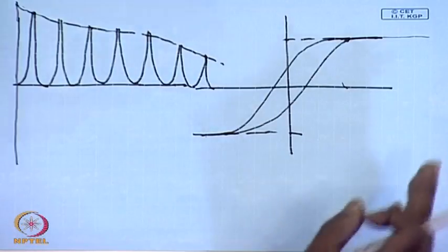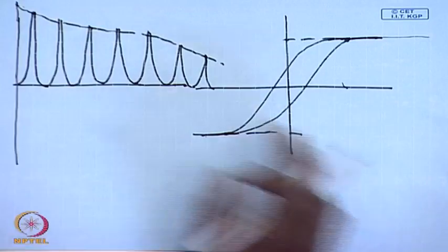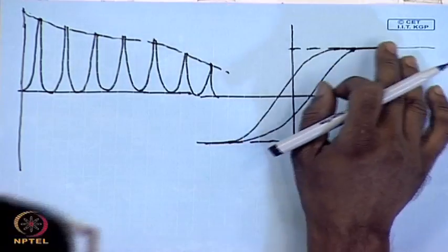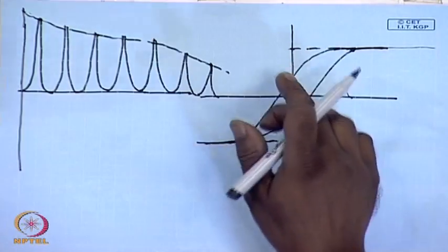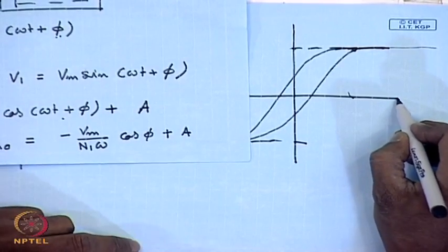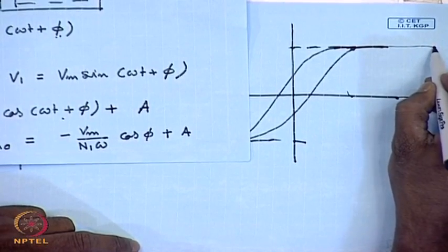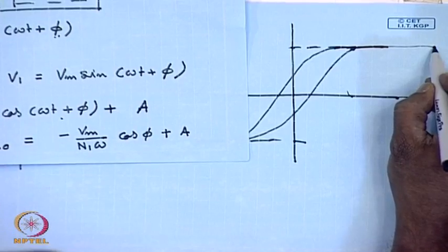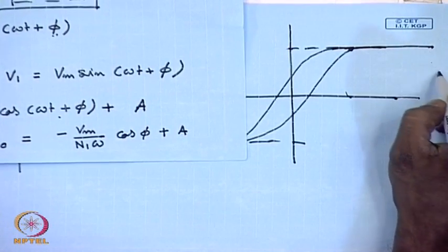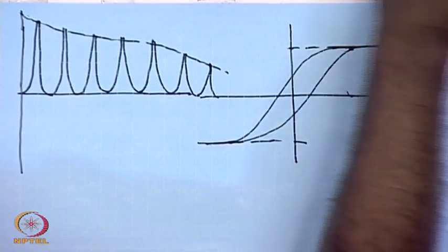Methods have been developed to detect the voltage waveform and switch transformers accordingly. Please note that the situation will be worse if there is some residual magnetism in the flux, because in that case the peak value can be even larger than twice the steady state peak. So, the single phase transformer protection device should withstand this magnetization current.